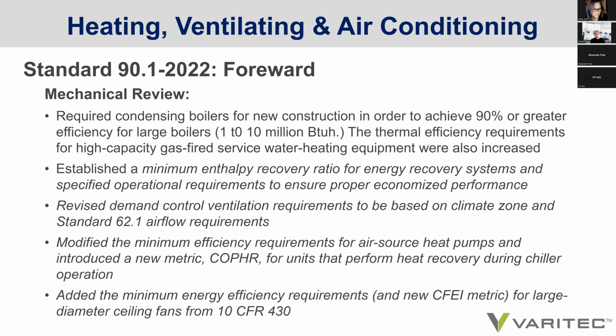language provides for systems. Other items addressed within the standard that we just don't have time to review or go into in any detail are as follows. Required condensing boilers for new construction in order to achieve 90% or greater efficiency for large boilers of 1 to 10 million BTUs. Established a minimum enthalpy recovery ratio for energy recovery systems and specified operational requirements to ensure proper economized performance. Revised demand control ventilation requirements to be based on climate zone and Standard 62.1 airflow requirements. Modified the minimum efficiency requirements for air source heat pumps, and introduced a new metric of COPHR for units that perform heat recovery during chiller operation. And there's now language for minimum energy efficiency requirements for large diameter ceiling fans.